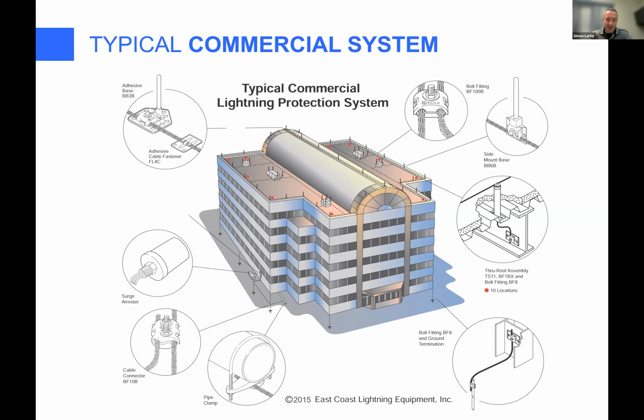You have got, upper left, adhesive bases. Those are good for gluing down to a membrane roof surface or the top of a parapet coping, something like that. You've got the conductor running between, you've got the conductor fasteners, you've got the bonding connectors. In this particular instance, the structural steel framework of the building is being used as a down conductor. You are allowed to do that. If the steel is 4.8 millimeters thick or greater, you can use it as a lightning conductor. So in this example diagram, we're using the steel as a down conductor.